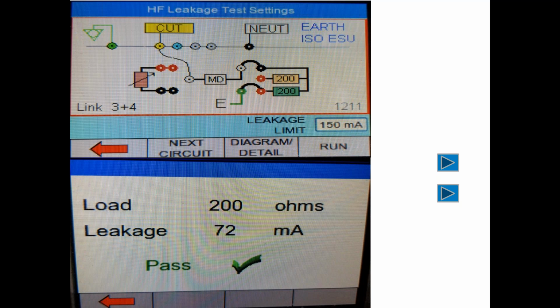So the message here really is, if you're doing this test and you're getting a failure, especially a close failure to the limit, just make sure that your leads are not coiled up anywhere, that there's no capacitance being added by running cables across a chassis anywhere. Just make sure they're nice and free and loose, as short as possible, and quite often you'll be able to get it to a passing state.